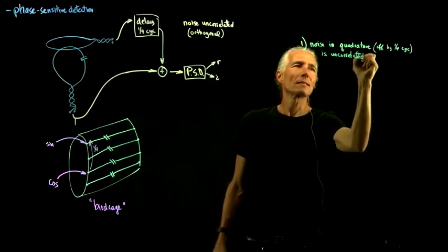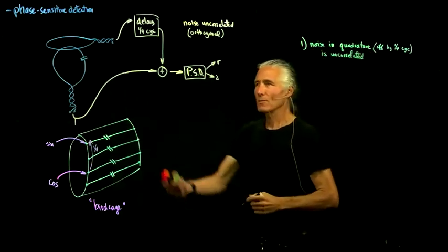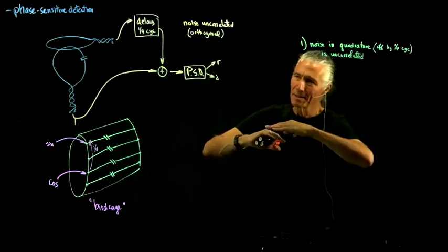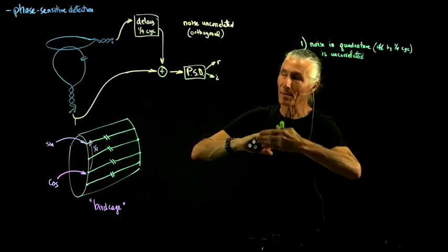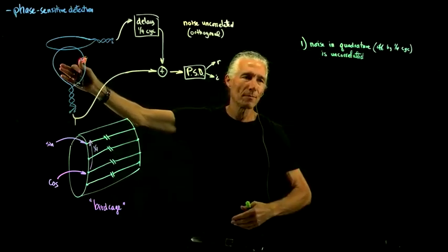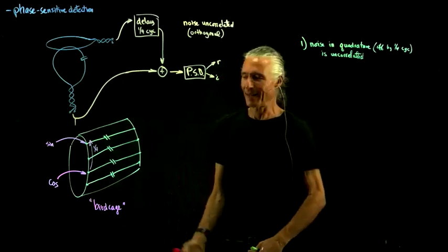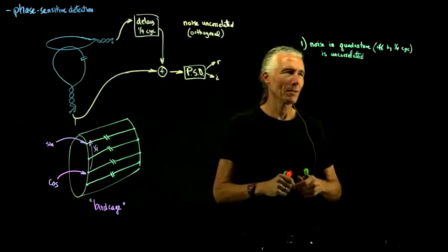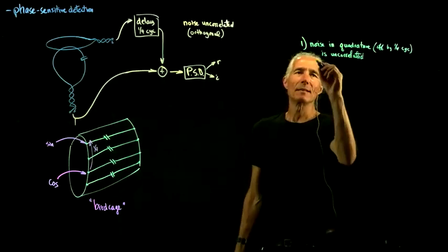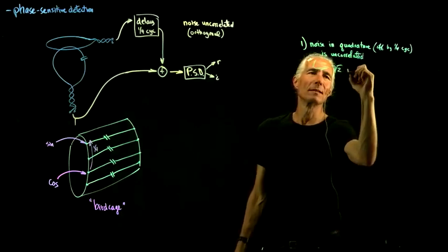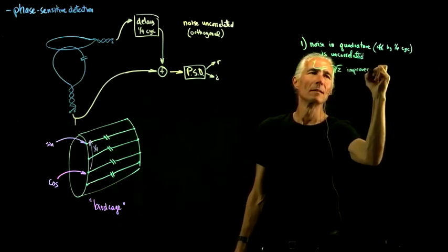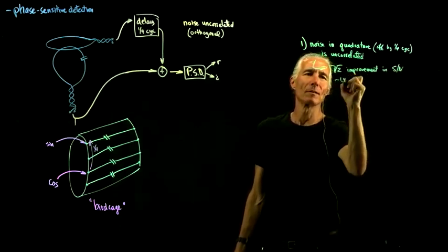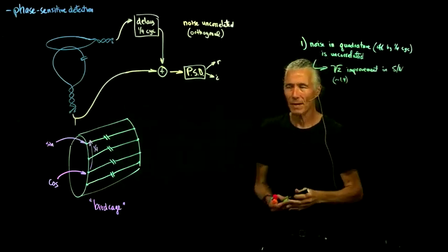And so definitely, because it's uncorrelated, it's advantageous to have a second coil. Now, unfortunately, of course, if you make another coil on the other side of the head, its noise is going to be correlated with a vertical coil, so you only get 2 cracks at it. There's only 2 possible uncorrelated positions of the coil. But it makes sense. You basically get a square root of 2 improvement in signal to noise, so it's about 1.4 by using 2 coils instead of 1.